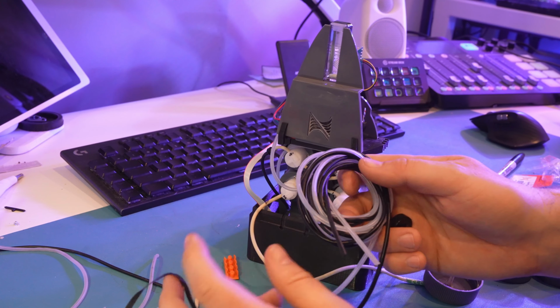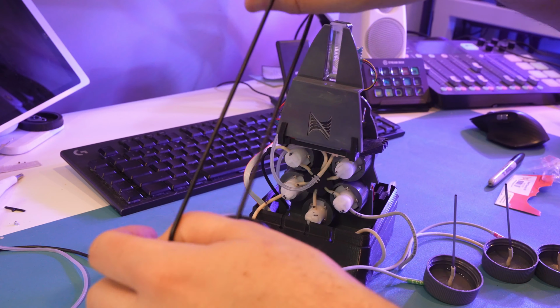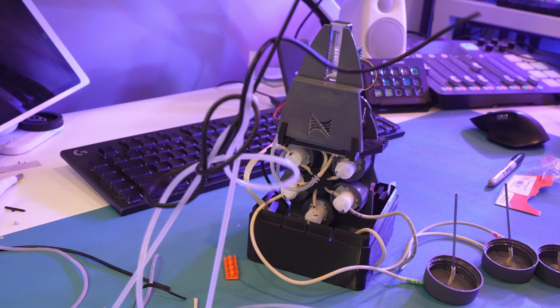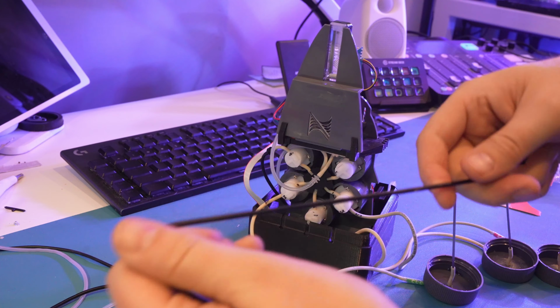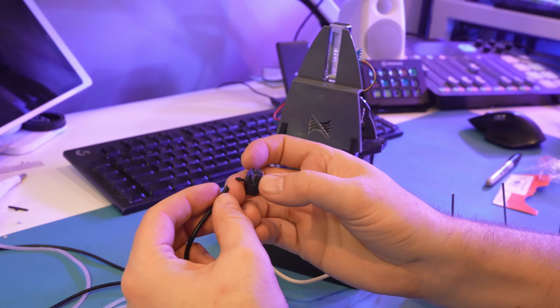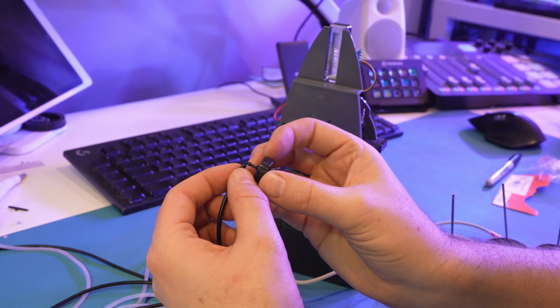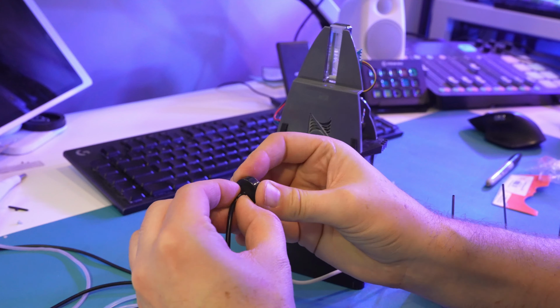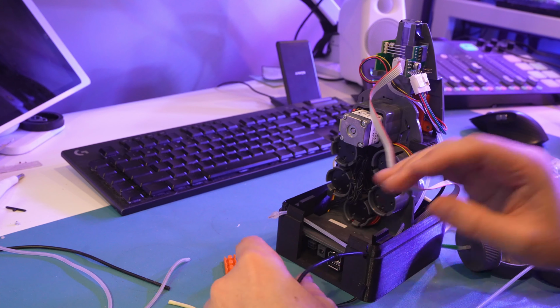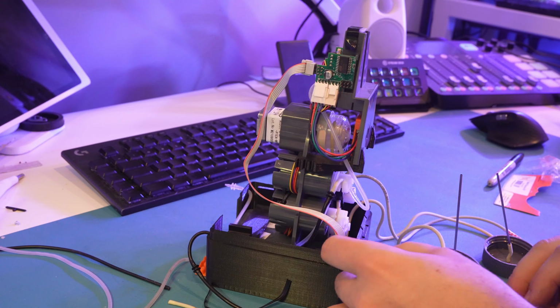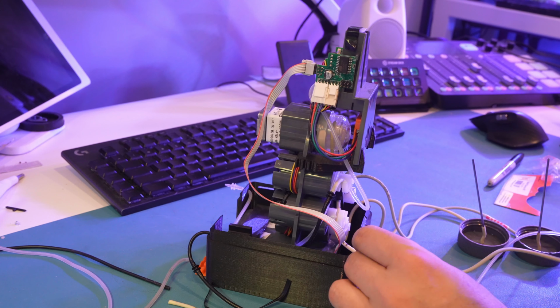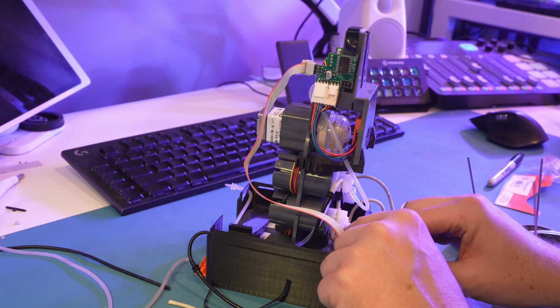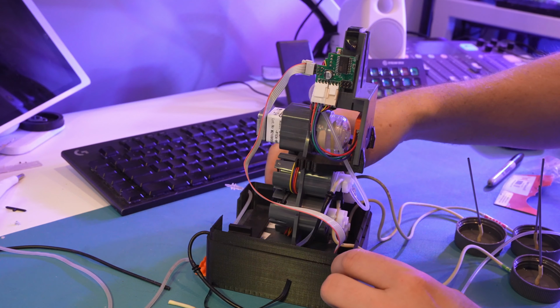And we of course have our new reagent lines. I don't know if I'm going to use the waste line per se, but I am most definitely going to be using a new sample intake line, and might as well use the new little filter that comes with it. It does have a little tiny arrow for which way it flows, so we'll put this on the intake. Now another thing to note, you will have to recalibrate everything on this, so it is a good idea to make sure that you have a fresh pack of reagents waiting and ready.